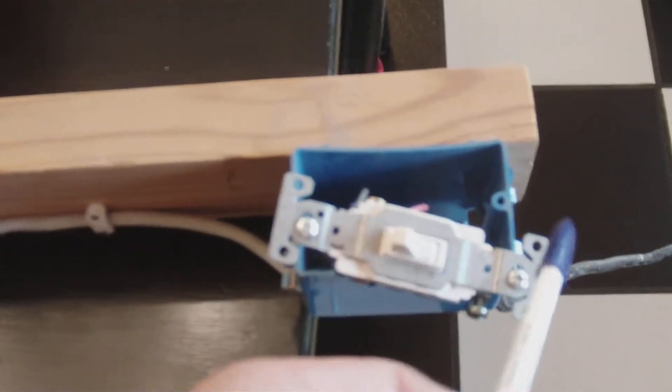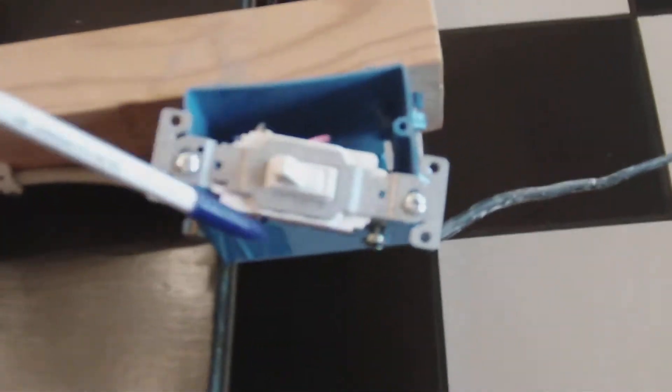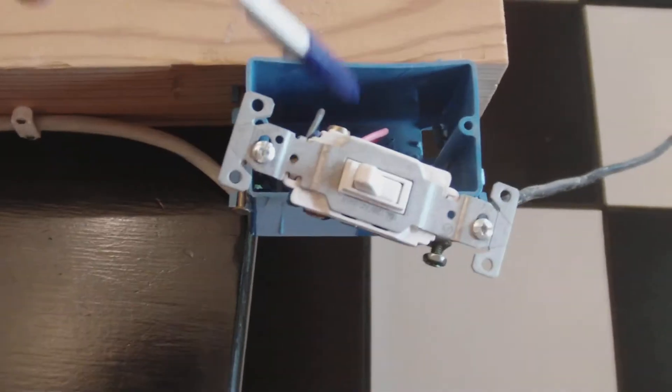So to go over it real quick, the black power wire coming into the first three-way switch is connected to the black screw, which is right here. The other two wires coming from the traveler makes no difference. Connect them to either side.